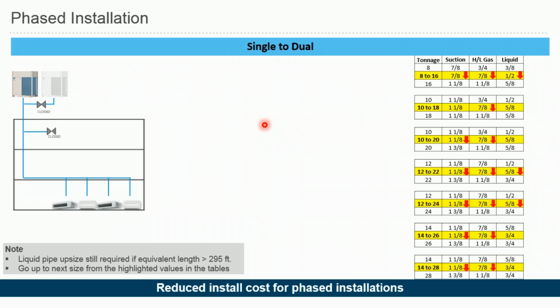So we basically asked ourselves how we could reduce this minimum connection ratio limitation, maybe below 50% at the earlier stage of the project. There are a lot of challenges when you try to do that. There's a chance that you might reduce the reliability of the operation with these lower connection ratios, because there will be a lot of refrigerant management issues. You will be facing oil return problems, very likely.